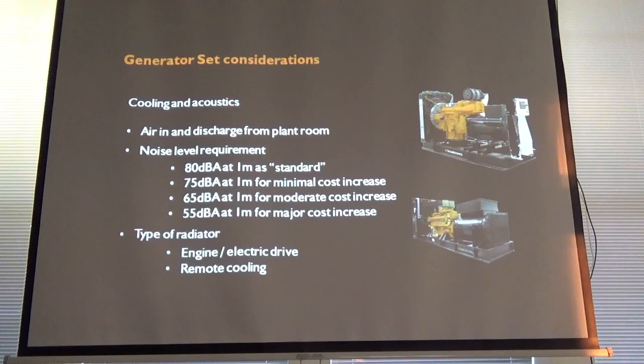So all you've done by moving that set-mounted radiator is increase your interdependency on other kit and equipment. What if it's an 11 kV unit? Those fans will run at LV, that pump will run at LV. So then you've got to actually go to a switchboard, then via a transformer to then feed back to those units. You know, I like it simple.